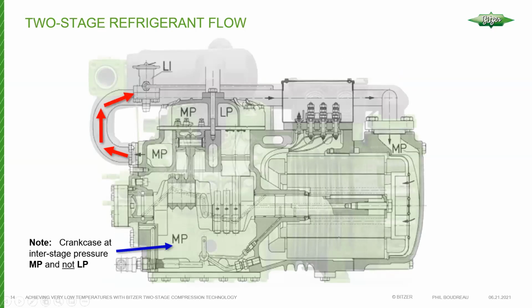Now we're going to continue from this mixing pipe. You can see the red arrows. We have fairly warm refrigerant leaving the low stage, and it travels through the mixing pipe all the way to the back of the motor barrel. And the injection valve, in this case, as I said, a liquid injection, is the simplest way to achieve this. It is the minimum requirement. We need to, at the very least, have a liquid injection valve, but a better mode would be subcooling. It will get you higher efficiencies and capacities. But I'll explain the difference between the two and how we connect them.